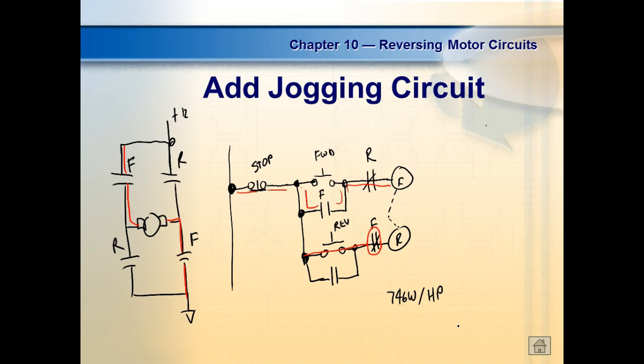Solid states, we got that little turn wheel on there, we can set it, right? And if we got heater overloads like we have, then normally what you would do is if you buy a reversing starter, it would have the overloads built into it, right here. You would have one set of overloads for both starters, because it's controlling the same motor.